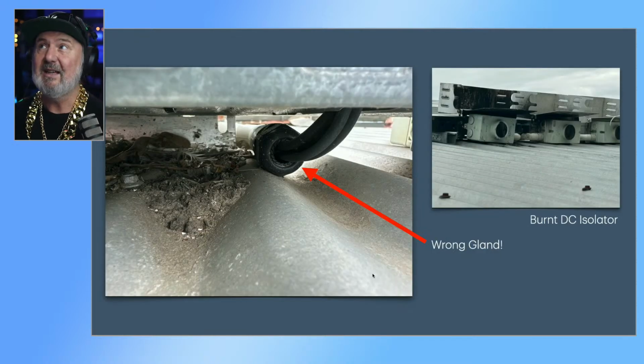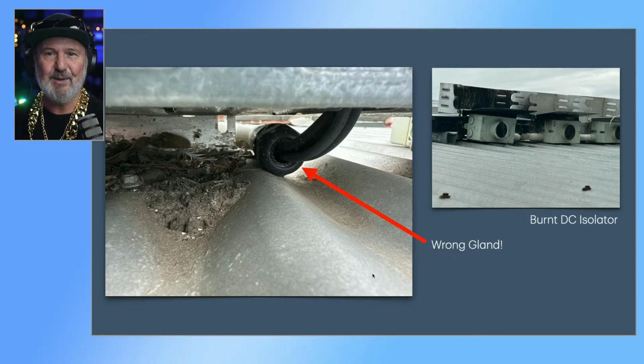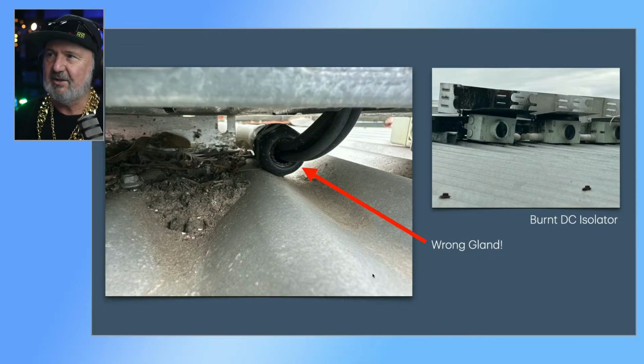All right, now we're coming to the end of today, actually, and I had a few discussions with one of my viewers today, and they sent in a few pictures, and this one got me. He was investigating a rather large commercial system that had caught fire, and he took a few pictures. Stephen will be very familiar with this problem, probably. People who haven't done the right thing. That's a gland, but it's for a single conductor, and a rather large one at that. So it's providing no protection from water ingress. And as you can see from the side picture, the isolator adjacent to the inverter caught fire because it just would have filled up with water.